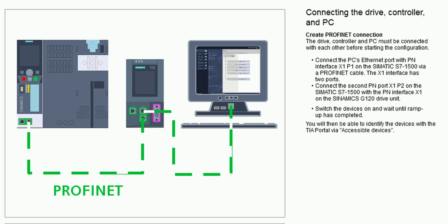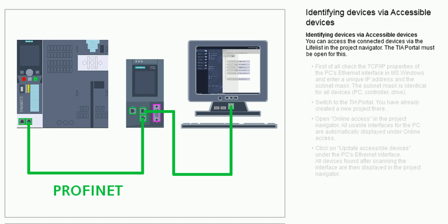Switch the devices on and wait until ramp-up has completed. You will then be able to identify the devices with the TIA portal via Accessible Devices. Identifying devices via Accessible Devices. You can access the connected devices via the life list in the Project Navigator. The TIA portal must be open for this.